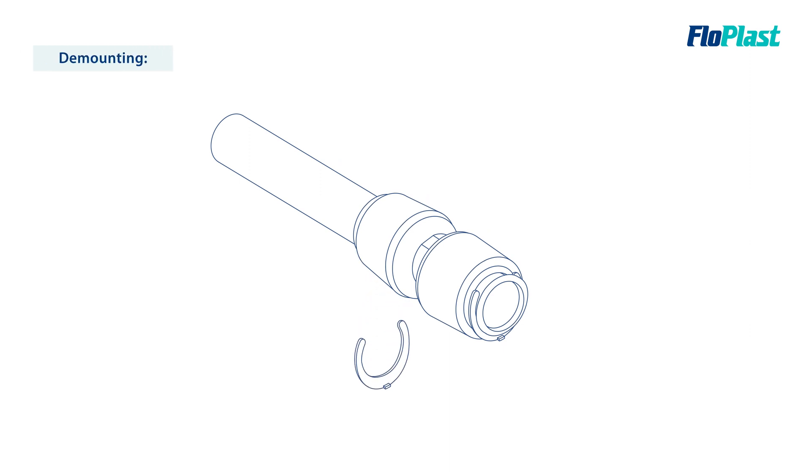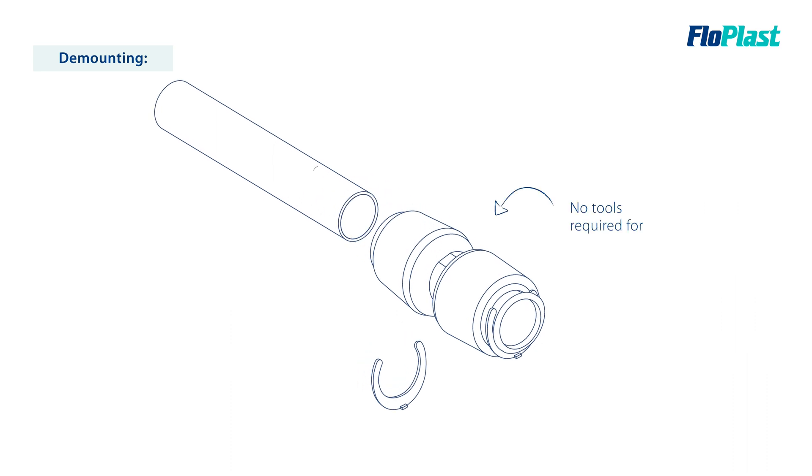When it comes to demounting the FloFit Plus system, you first need to remove the collet clip and loosen the cap on the fitting. Pull the pipe back slightly, then push the collet face towards the body of the fitting. No tools should be required to dismantle FloFit Plus fittings.